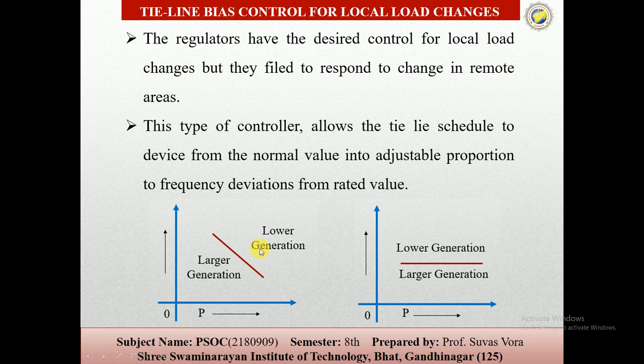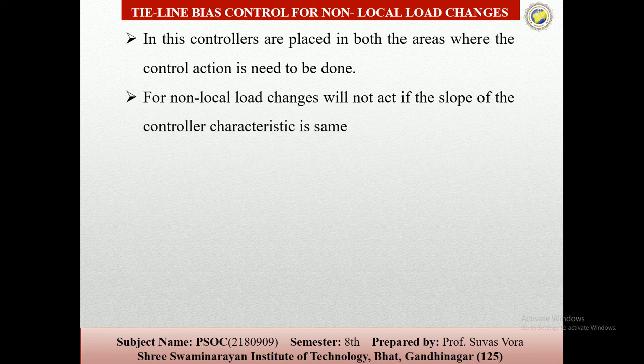In a similar way, the tie line controls for the non-local load changes. In this method, the tie line bias controls are placed in both areas where the control action is required. The controller will not act for non-local load changes if the slope of the controller characteristic is the same as the governing characteristic. If the characteristic is the same, it will not be affected.